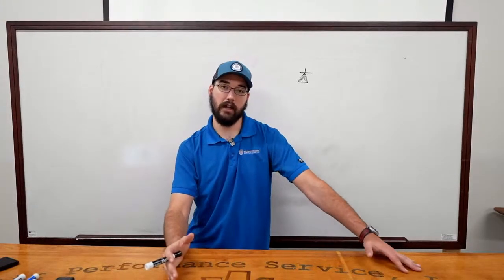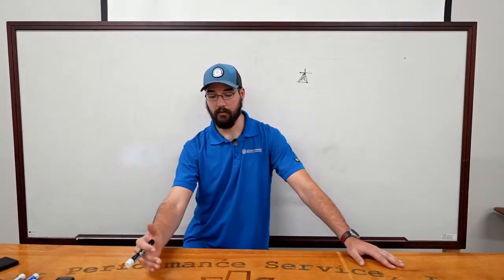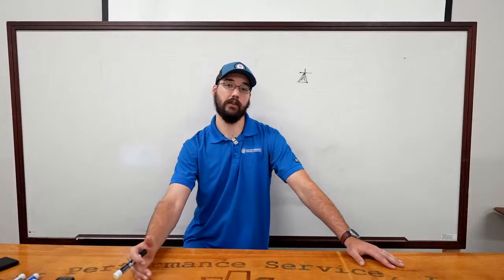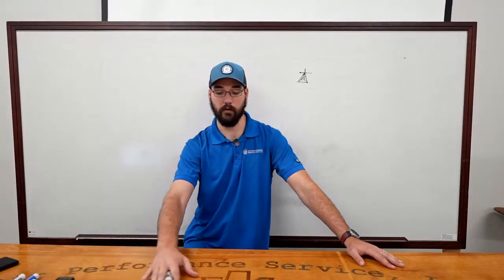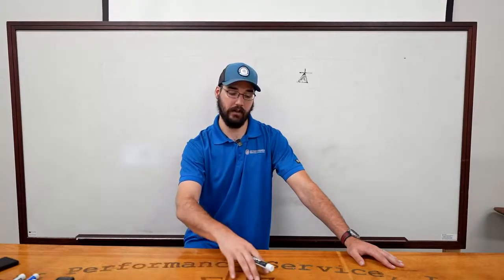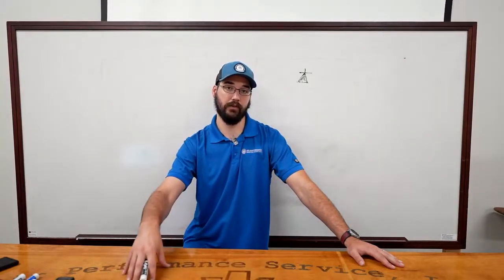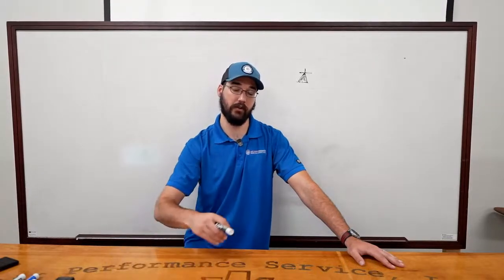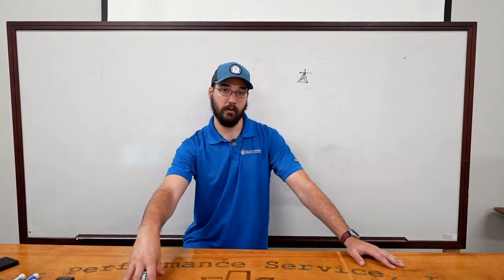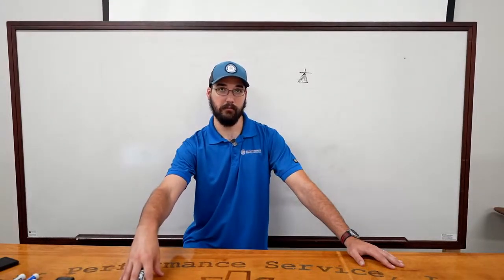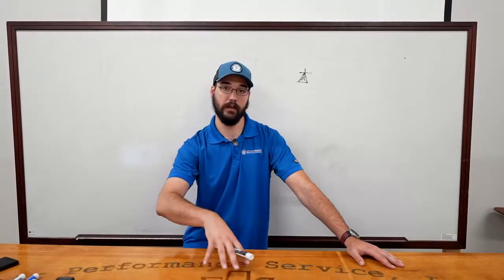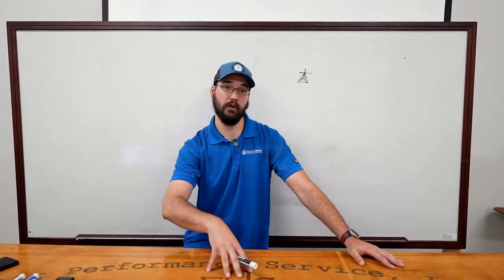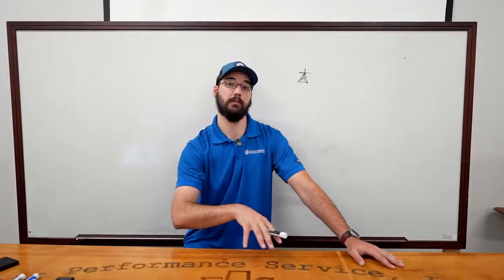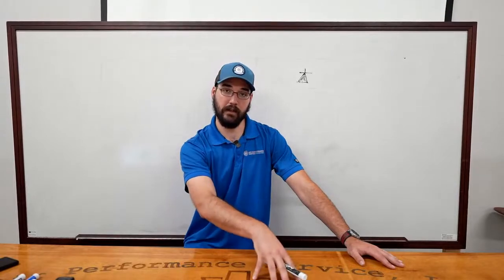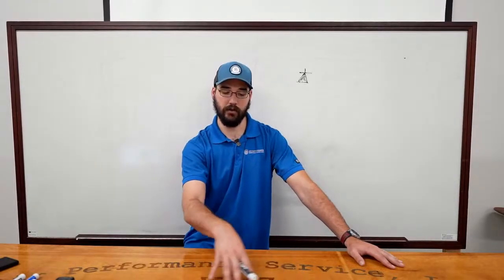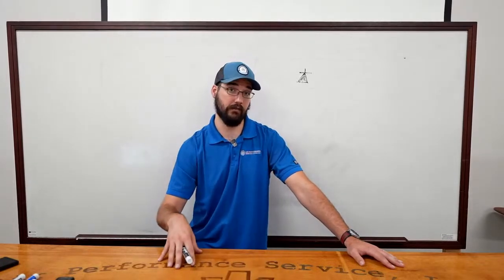So by the fourth call out, I ended up getting on with one of the more senior level tech support guys from LG, and he was the one that informed me that they actually have an internal policy that anytime we start to change those components, they recommend on a factory level doing it all together, because what they've seen is a bad blower will cause problems with the PCB or the fan board, and that will end up frying those components, even though they may not be the direct issue when you're troubleshooting. So then you go out and you replace that component, and exactly what happened to me, right? It turns into this chain reaction, and everything is causing everything else to fail.